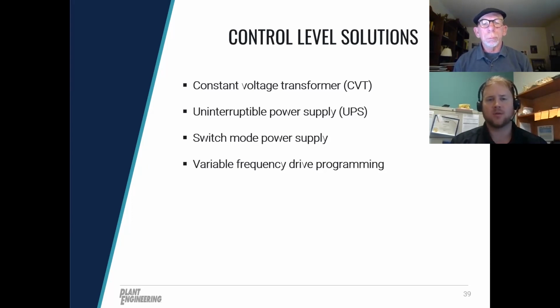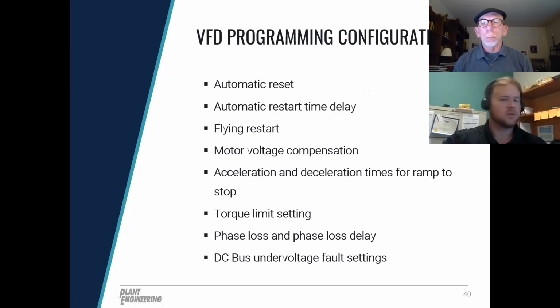If you're having momentary interruptions that impact a variable frequency drive specifically, you need to check that it's programmed for ride-through capability. And that's where we're going to close the presentation. So we're going to go through a quick example of ride-through programming of a variable frequency drive. If you've ever programmed a VFD, drives have many parameters. They can be configured in a lot of different ways. I always recommend working with the drive manufacturer directly to program for ride-through, depending on your application and what kind of power quality events you may be seeing. And each drive is different, so a configuration may work for one drive, but it may not necessarily work for another.